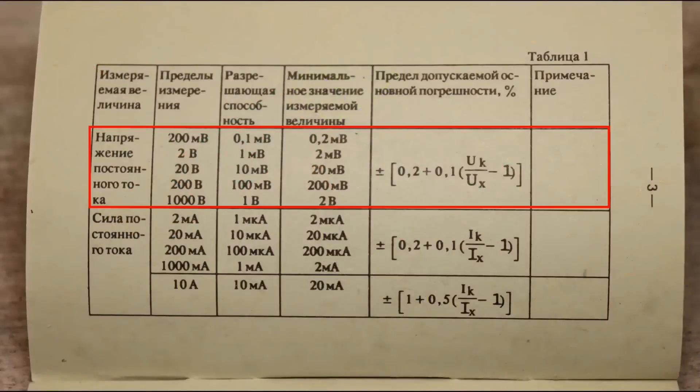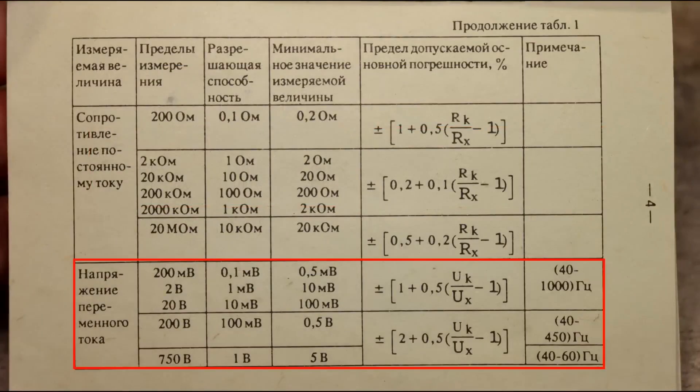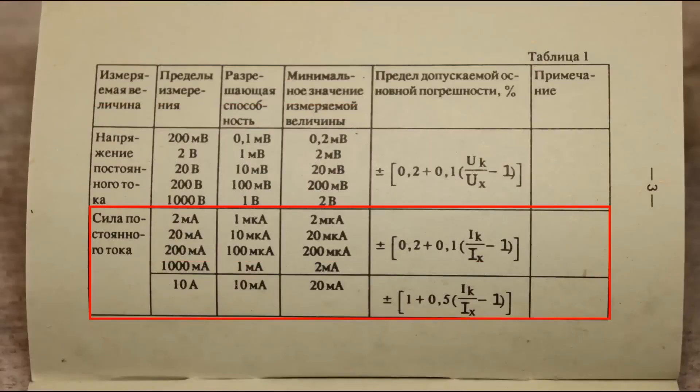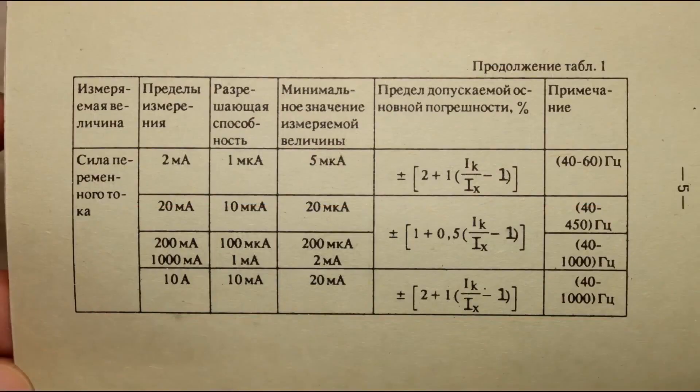It can measure direct voltage up to 1000 volts with an average tolerance of 0.2%, an alternating voltage up to 750 volts with the frequency of the measured voltage ranging from 40 Hz to 1 kHz, with a tolerance of 1.2%. Resistance up to 20 megaohms, 0.2%. Direct current up to 10 Amperes, with a tolerance of 1%, and in the range up to 1 Ampere, only 0.2%. An alternating current up to 10 Amperes, with a tolerance of 1% in the range up to 1 Ampere, and up to 2% in the range from 1 to 10 Amperes.